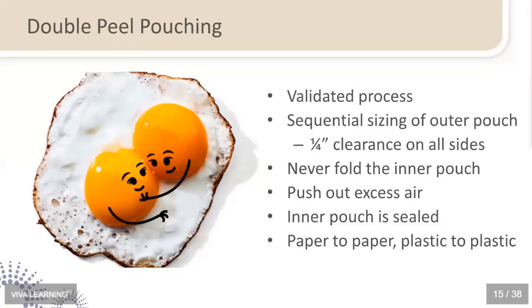If you are using double pouching, you're going to use two different size pouches. They need to be sequential sizing. Obviously, the outer pouch is larger because there has to be a 1/4 inch clearance on all sides of the smaller pouch. The two sides, top and bottom, have to have a 1/4 inch clearance. You can't sort of fold, bend, finagle that smaller pouch inside the larger one. It has to be appropriately sized.